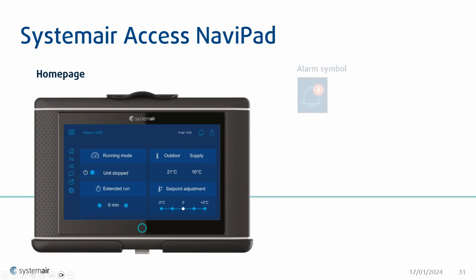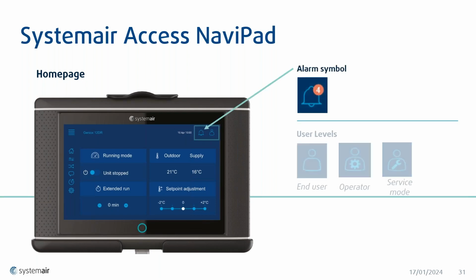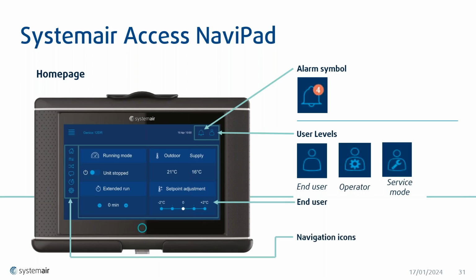When we look at the NaviPad itself, this is what gets installed on the unit. I'd also like to let you know that this is an IP55 module, so it can be installed outdoors. It is waterproof. You have your home screen, your home page. You have your different user levels: your end user, your operator, and then your service mode, and all your standard navigation modes that you would have with this. When the unit is configured and the sequence of operations is selected from the actual selection program as well, it is uploaded to the SystemAir Access control system. Once the unit is manufactured and the actual control system is made specifically for that unit, it is then uploaded to SystemAir Cloud.